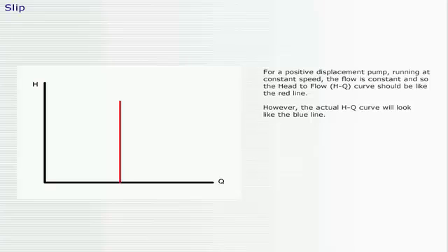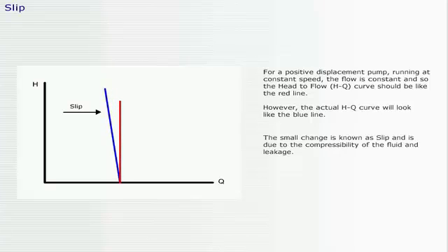For a positive displacement pump running at constant speed, the flow is constant, and so the head-to-flow curve should be like the red line. However, the actual head-to-flow curve will look like the blue line. The small change is known as slip, and is due to the compressibility of the fluid and leakage.